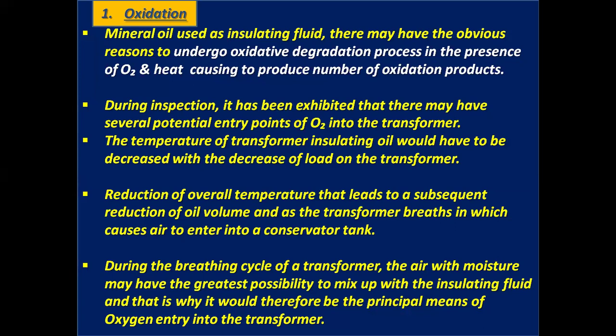Number one, oxidation. Mineral oil used as insulating fluid may undergo an oxidative degradation process in the presence of oxygen and heat, producing a number of oxidation products. During inspection, it has been found that there are several potential entry points of oxygen into the transformer. The temperature of transformer insulating oil decreases with the decrease of load on the transformer. The reduction of overall temperature leads to a subsequent reduction of oil volume, and as the transformer breathes in, air enters the conservator tank.